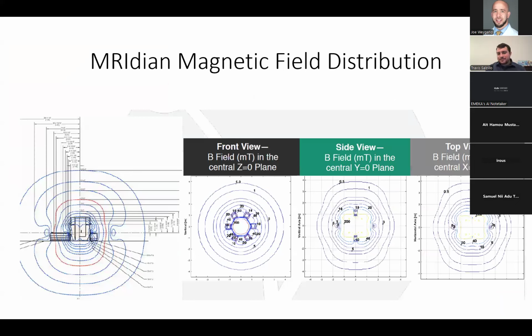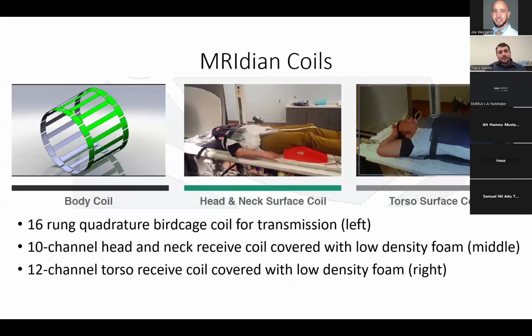This is just an overview of what the magnetic field gradients look like. Really what you need to take away from this is that it is very homogeneous, from all views. The coil system for the MRIdian is very good when compared to other units. They utilize the body coil, which is within the system itself, but they also have surface coils and dedicated head and neck coils, which conform very well to the anatomy of the patient. And so the better your conformality, the higher your image quality will be, especially when you already have a low field magnet to begin with.